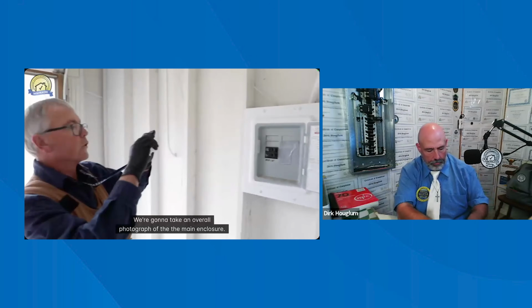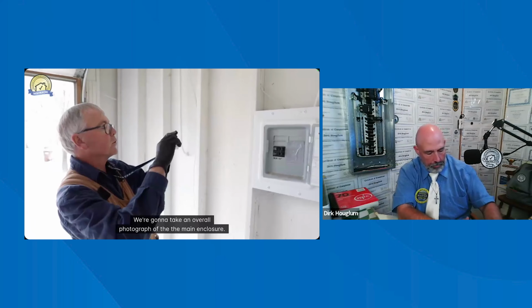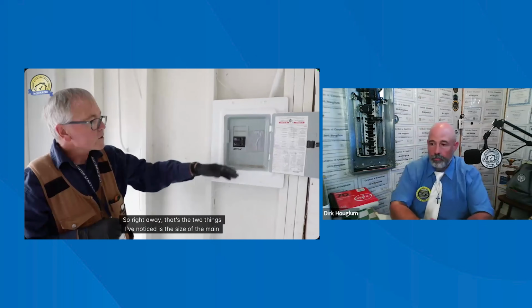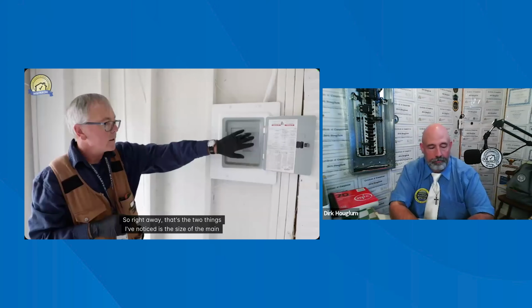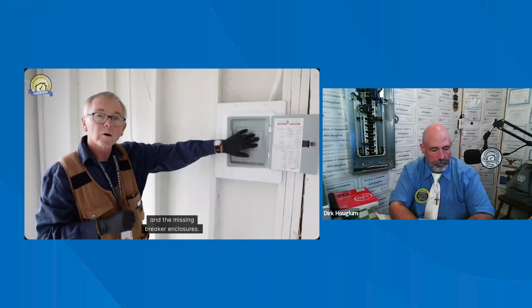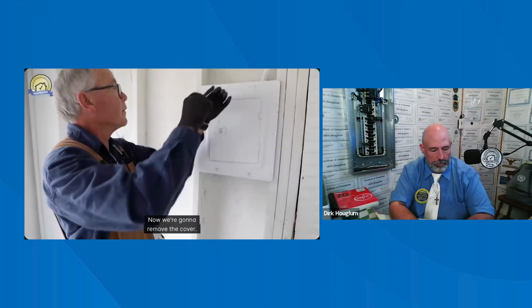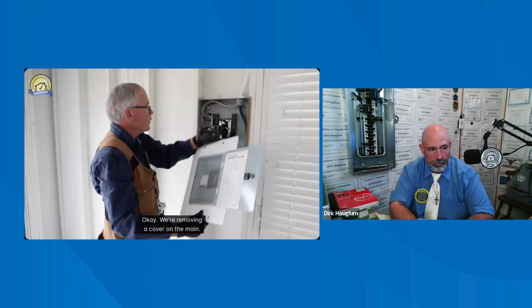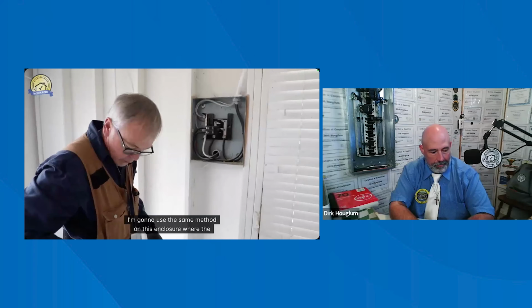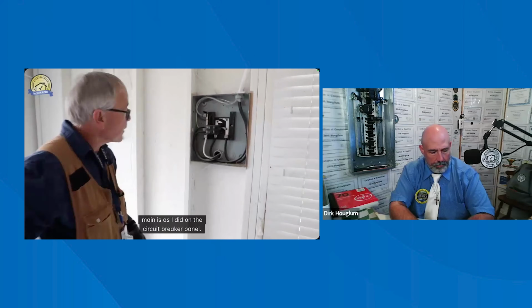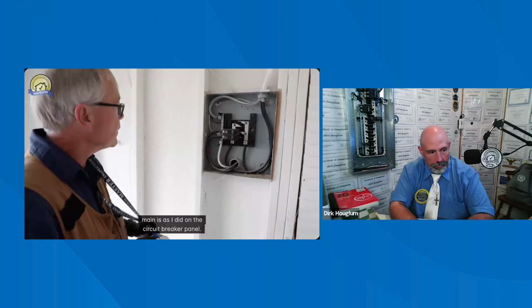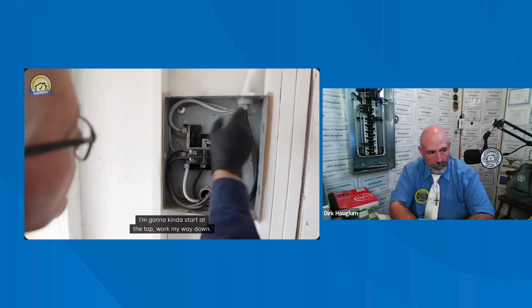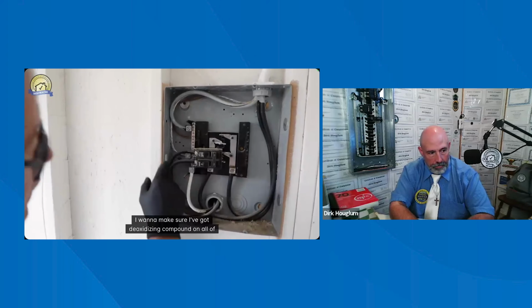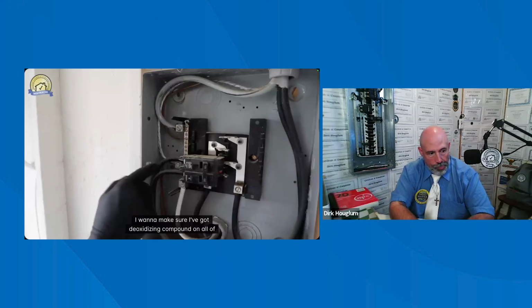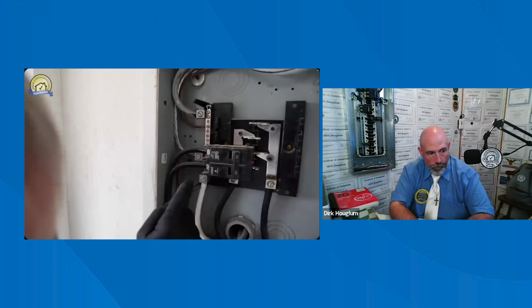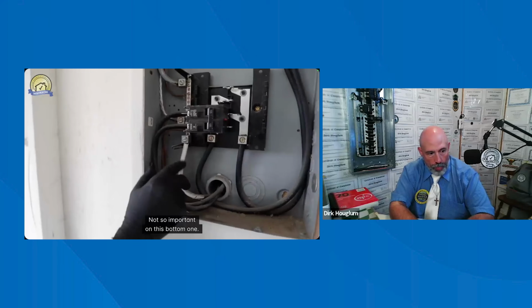I'm going to take an overall photograph of the main enclosure. So right away, those are the two things I've noticed: the size of the main and the missing breaker fillers. Now we're going to remove the cover. Okay, we're removing the cover on the main. I'm going to use the same method on this enclosure where the main is as I did on the circuit breaker panel. I'm going to start at the top and work my way down. I want to make sure I've got deoxidizing compound on all of the main lugs, and it looks like I do. Not so important on this bottom one.